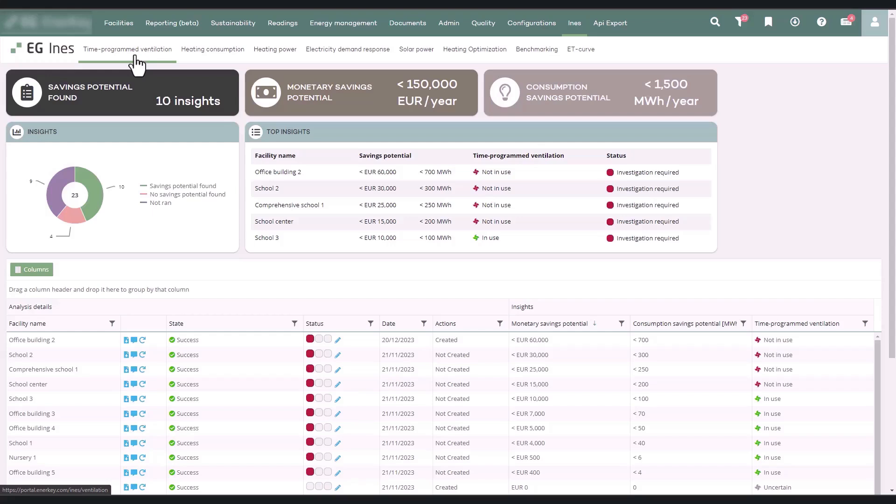Potential saving opportunities are identified based on the building's hourly energy and water consumption. The data is used to deduce ventilation running times and compare them against actual facility usage times based on water consumption. If water consumption data is not available at an hourly level, default operating times in non-residential buildings from 6 a.m. to 6 p.m. are used.